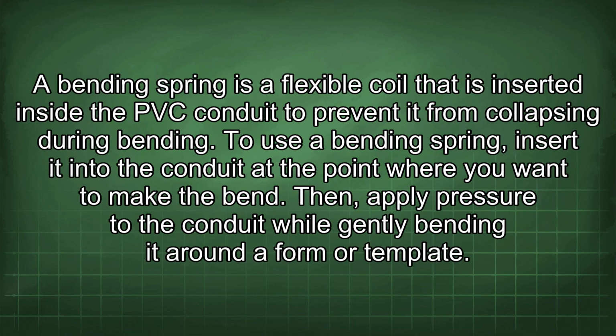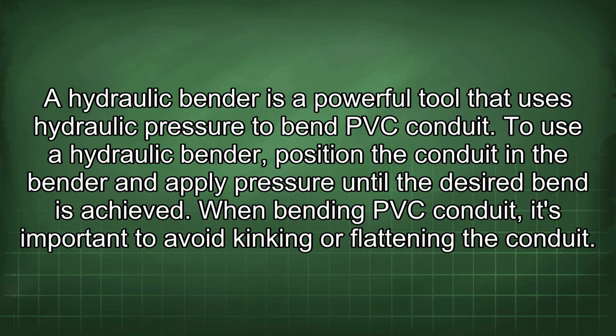A bending spring is a flexible coil that is inserted inside the PVC conduit to prevent it from collapsing during bending. To use a bending spring, insert it into the conduit at the point where you want to make the bend. Then apply pressure to the conduit while gently bending it around to form a template. A hydraulic bender is a powerful tool that uses hydraulic pressure to bend PVC conduit. To use a hydraulic bender, position the conduit in the bender and apply pressure until the desired bend is achieved.